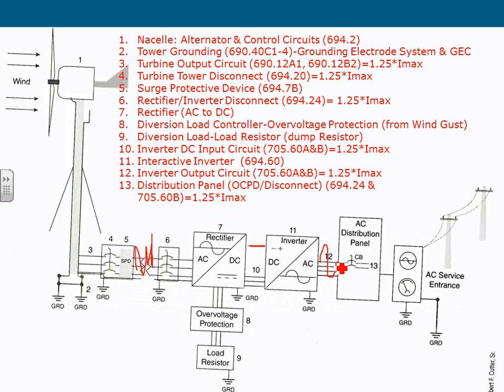So that inverter will monitor the grid, and if the grid is down, your system is down. But there are inverters that, if the grid is down, will isolate from the grid and connect you directly to another load, so it acts as backup power, basically. But if you're dumping on the grid, you have to have anti-islanding. Anti-islanding doesn't mean you dump your load. It means you isolate yourself from the grid. Now, what you do with the power is up to you.